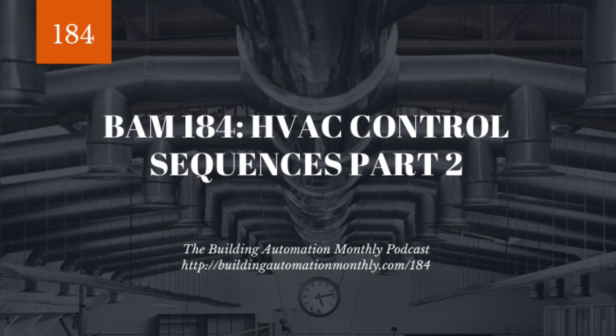But most of the time when you need outside air for ASHRAE 62.1, you're going to be utilizing a rooftop unit. When you have an IDF or MDF space that is not persistently occupied and you're not terribly concerned with outdoor air quality because you're not bringing in outdoor air, you can typically use a fan coil and that'll be just fine. Fan coils also, most of the time, once again, I'm saying most of the time; you guys and gals email me, and I don't say absolute, so hey, you're hearing it.